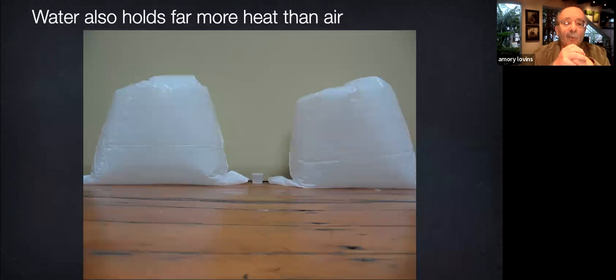And in case you forget that water has over 3,000 times the heat capacity of dry air per unit volume, here's a little visual reminder. Just remember the sight of these 2 big bags of air compared to that tiny cup of water that has the same heat capacity as all that air.